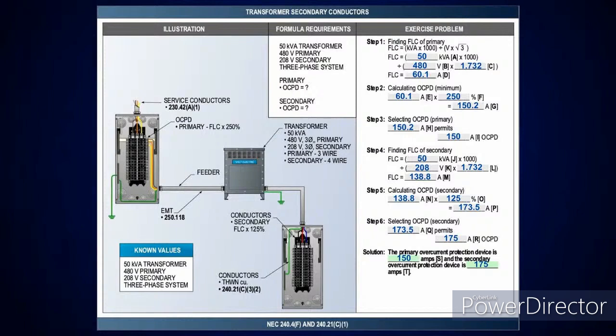Then I do the secondary, same calculation. The only difference is I'm going to divide by 360, which is the figure for the 208 volt 3-phase. That gives me 138.8 amps. Take it at 125%, which gives me 173.5. At 125% or less, you go up. The next size above that in table 240.6(A) is a 175 amp overcurrent device.